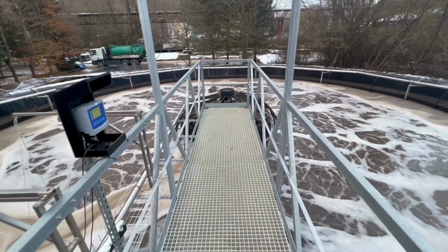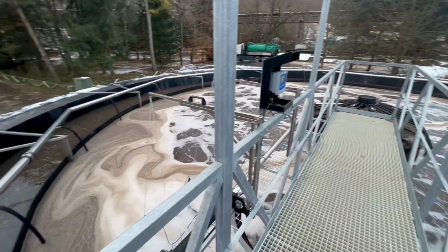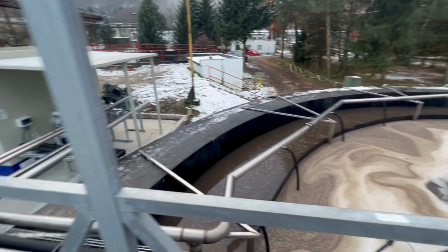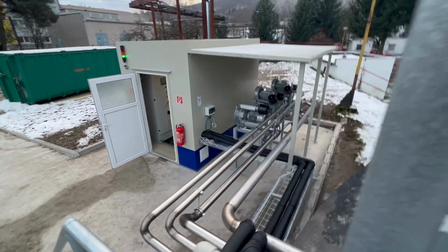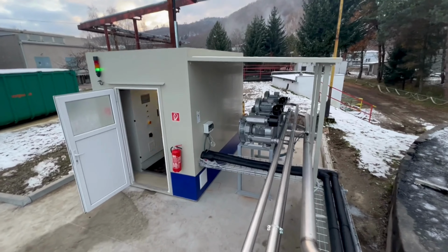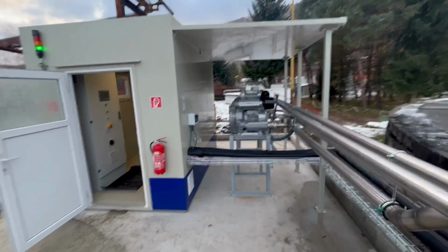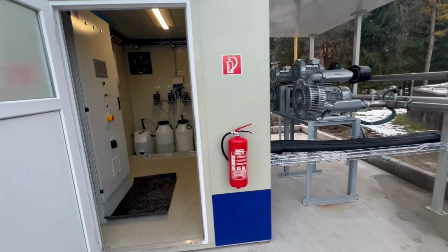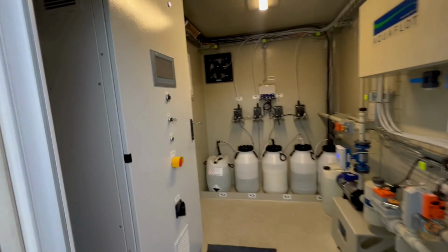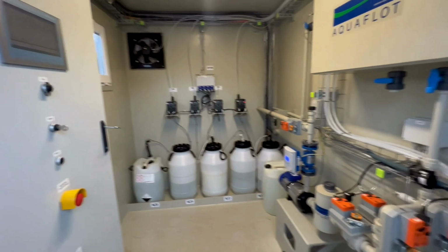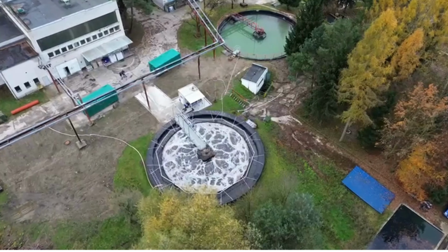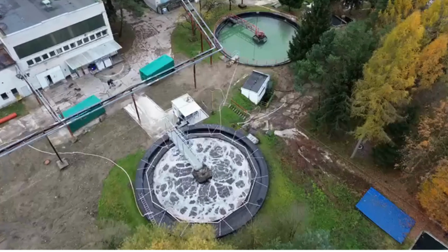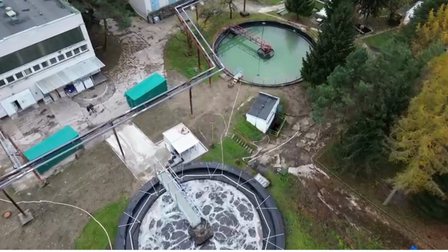The residual organic pollution requires another step to reduce it. An optimal solution to provide for this is to include the MBR technology. It is a biological treatment process using ultrafiltration membrane separation. The system works with high concentrations and a more mature sludge. This combination enables the biological treatment of even harder to decompose organic substances. Ultrafiltration membranes thus allow the treatment of effluents with poorer separation properties.